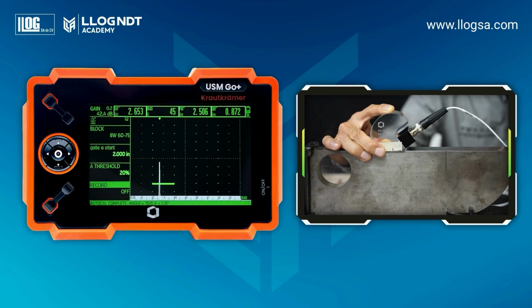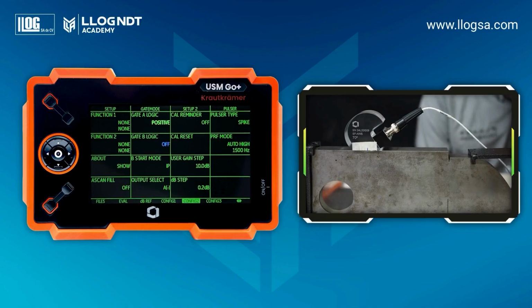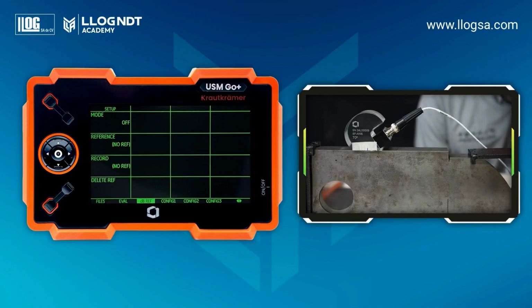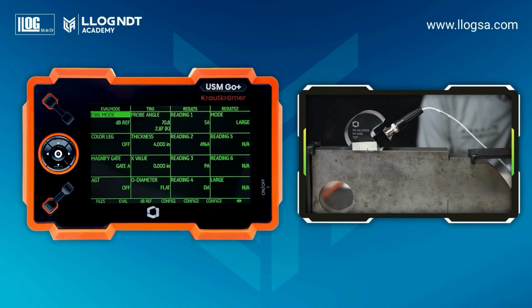At the bottom of the screen, a message will appear indicating that the angle auto-calibration has been successfully completed, and it will display the new calculated angle value. The allowed tolerance, according to document AWS D1.1, is plus or minus 2 degrees. Sensitivity adjustment. For the sensitivity adjustment, we will follow the procedure according to AWS D1.1. To begin, go to the second operating level and select the evaluation mode, AWS D1.1.